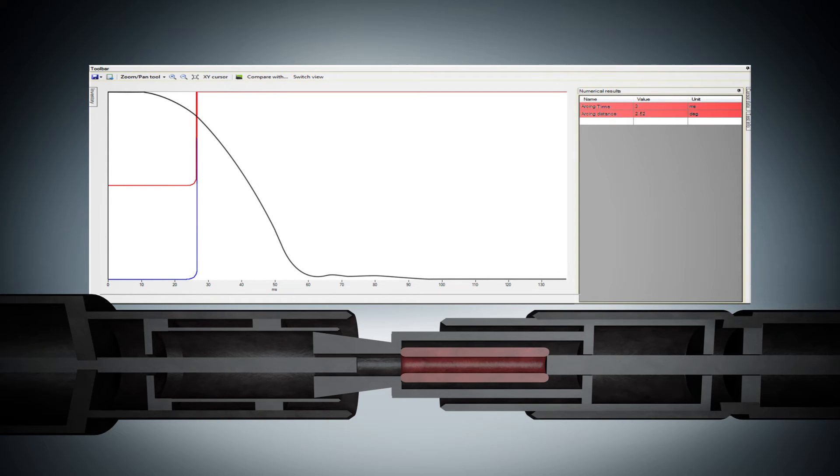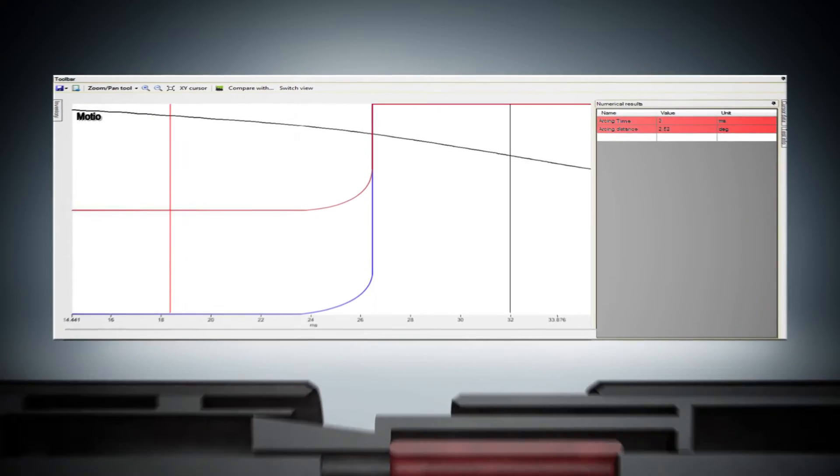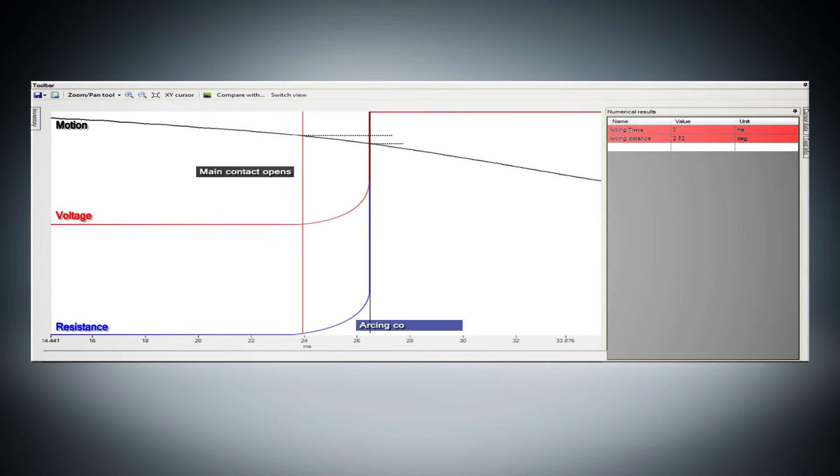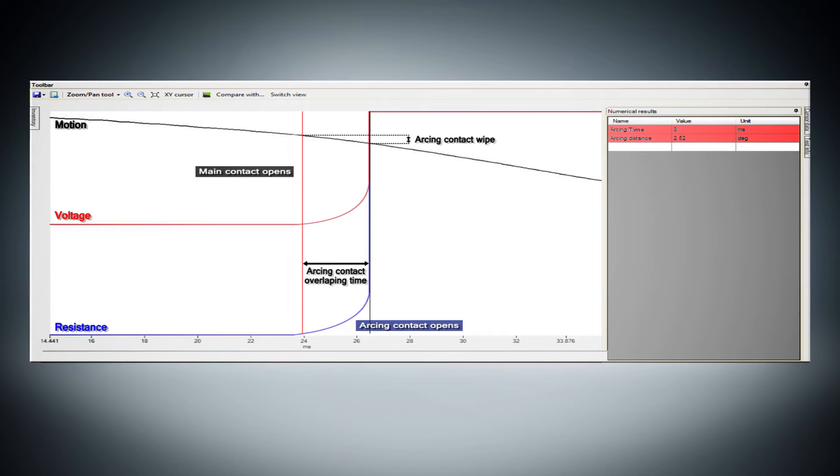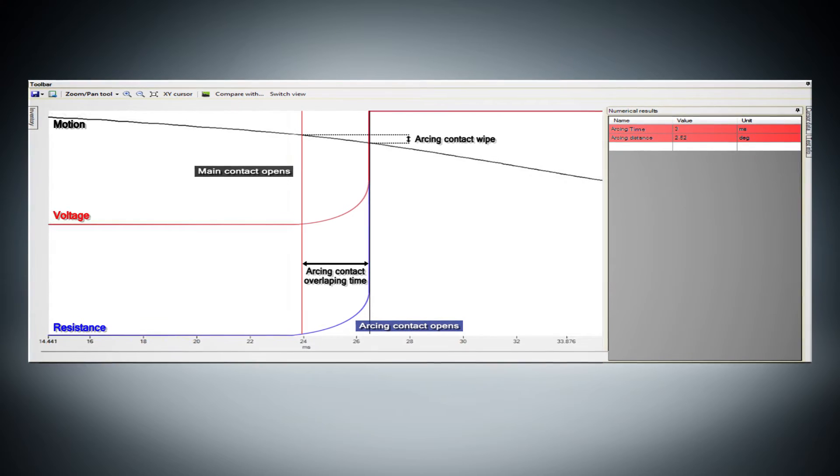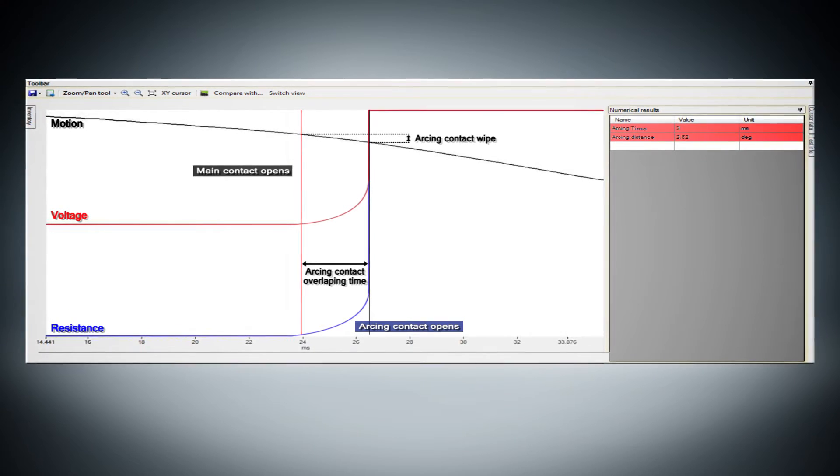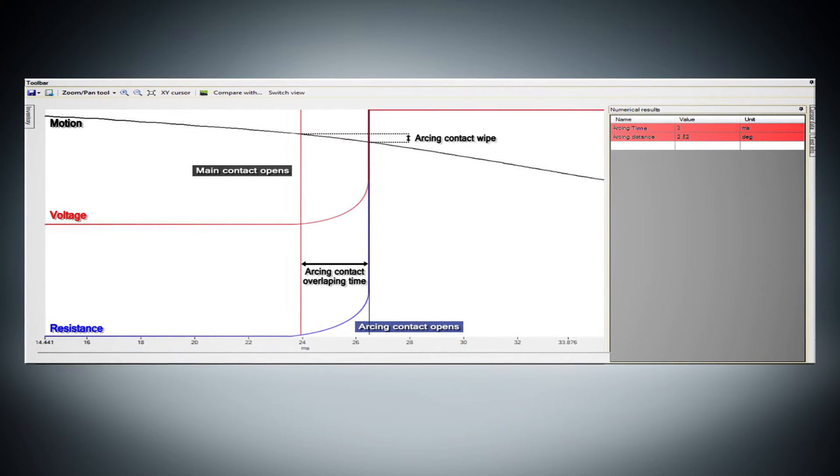The dynamic resistance measurement method measures variations in the contact resistance during the breaker operation. When the breaker contact motion is measured simultaneously with resistance, the results can be used to assess the wear or reduced length of the arcing contact.